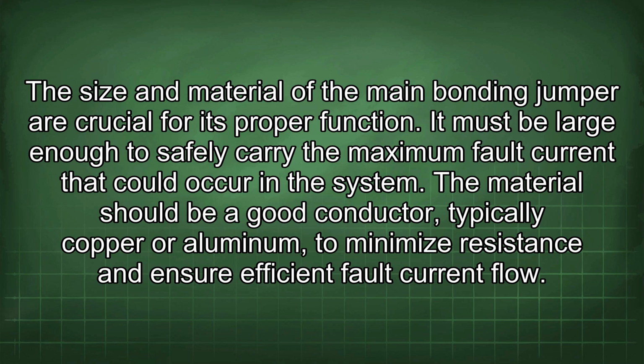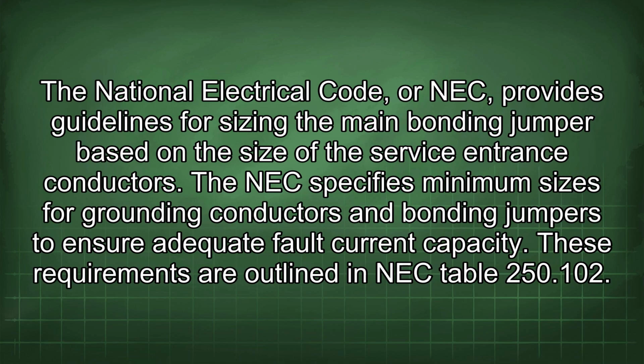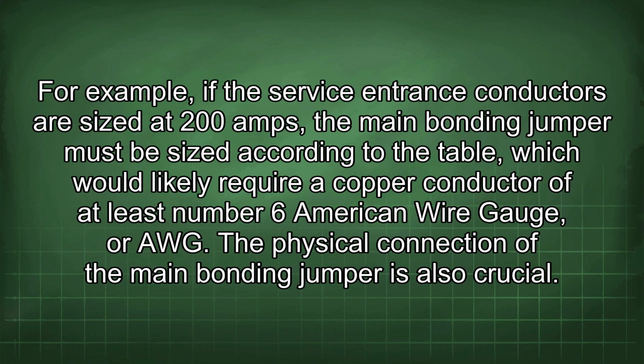The size and material of the main bonding jumper are crucial for its proper function. It must be large enough to safely carry the maximum fault current that could occur in the system. The material should be a good conductor, typically copper or aluminum, to minimize resistance and ensure efficient fault current flow. The National Electrical Code, or NEC, provides guidelines for sizing the main bonding jumper based on the size of the service entrance conductors. The NEC specifies minimum sizes for grounding conductors and bonding jumpers to ensure adequate fault current capacity. These requirements are outlined in NEC Table 250.102. For example, if the service entrance conductors are sized at 200 amps, the main bonding jumper must be sized according to the table, which would likely require a copper conductor of at least number 6 American wire gauge, or AWG.